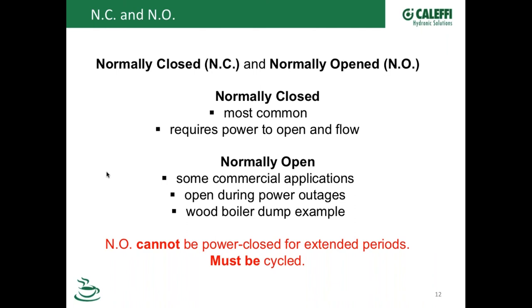Yeah, so we do get calls about the normally open valves pretty regularly. Like you mentioned, a lot of commercial applications are using normally open actuators and valves. There are thermostats out there that are kind of reverse operation type thermostats that can be used with normally open valves. Like you said, a lot of times it's being used where they want it to fail open and overheat as opposed to fail closed and cause freezing or damage to a property. From there though, just like it says at the bottom of your slide, they cannot be powered closed for an extended period of time.